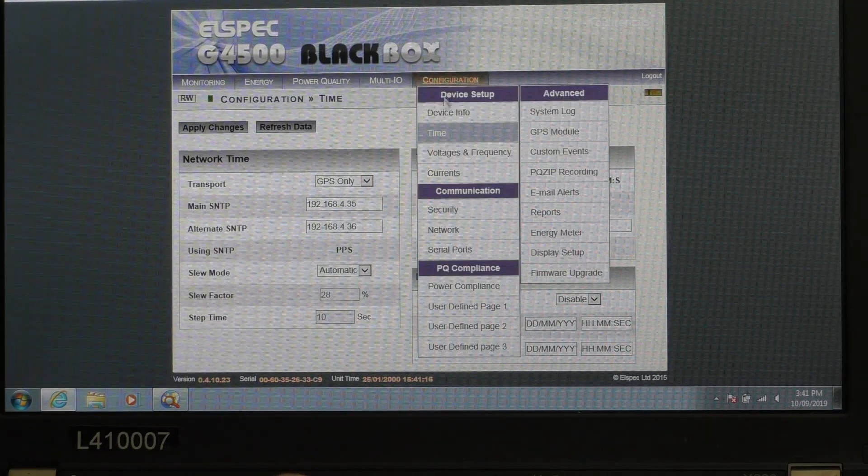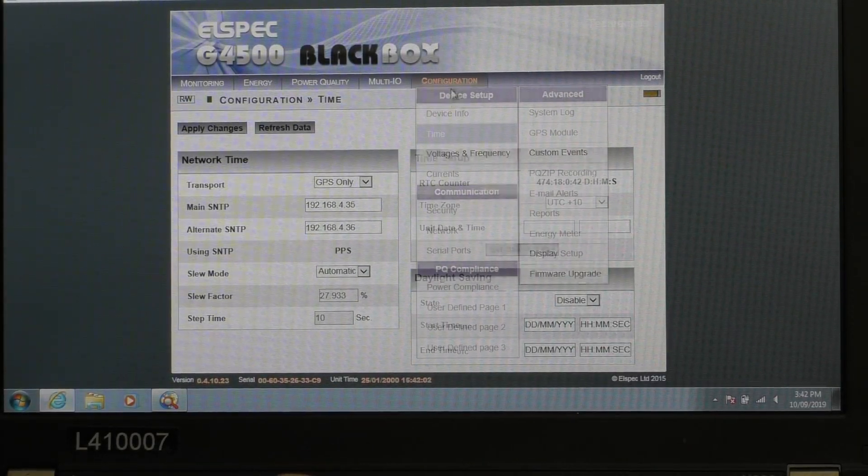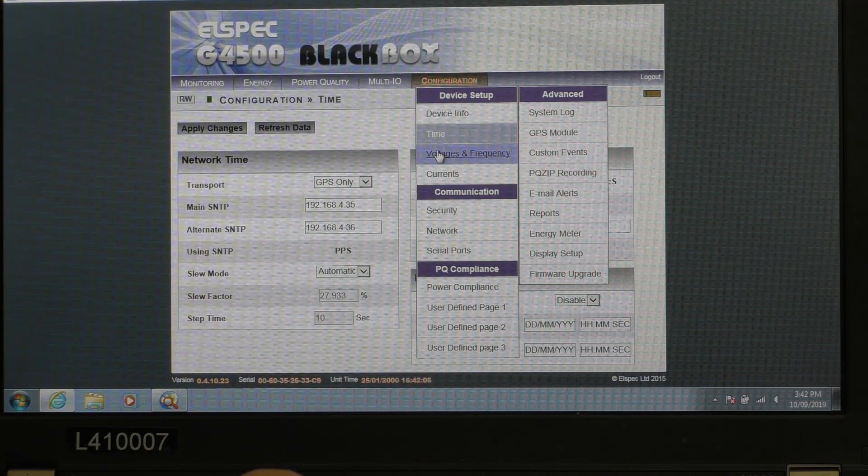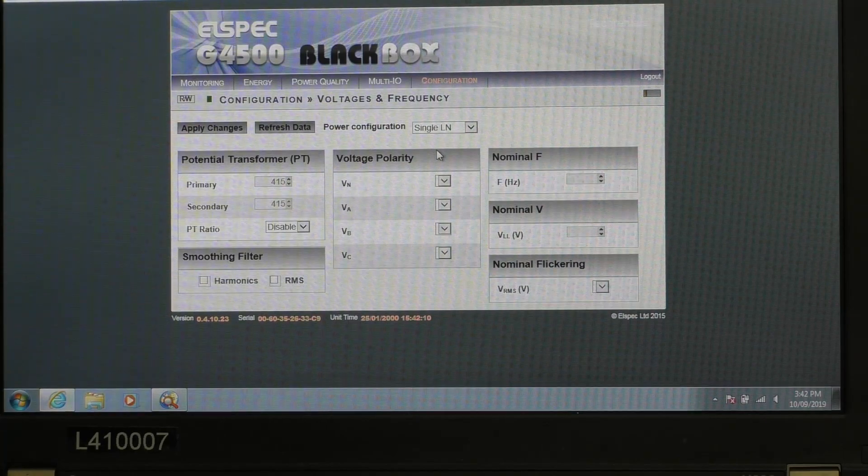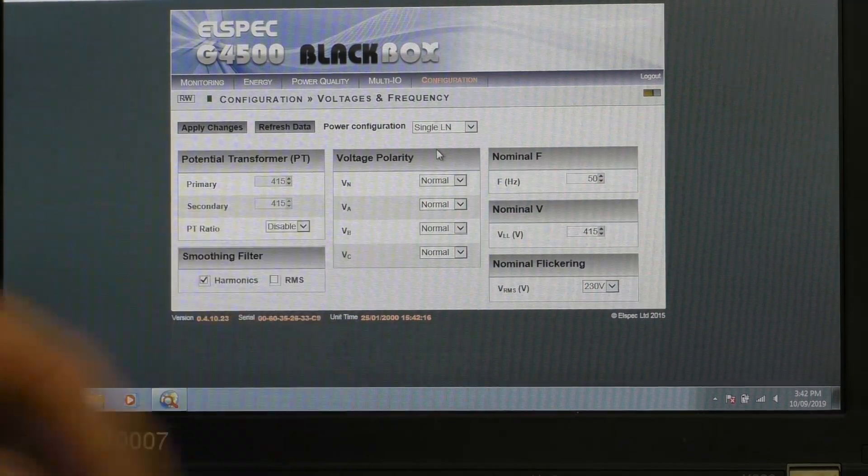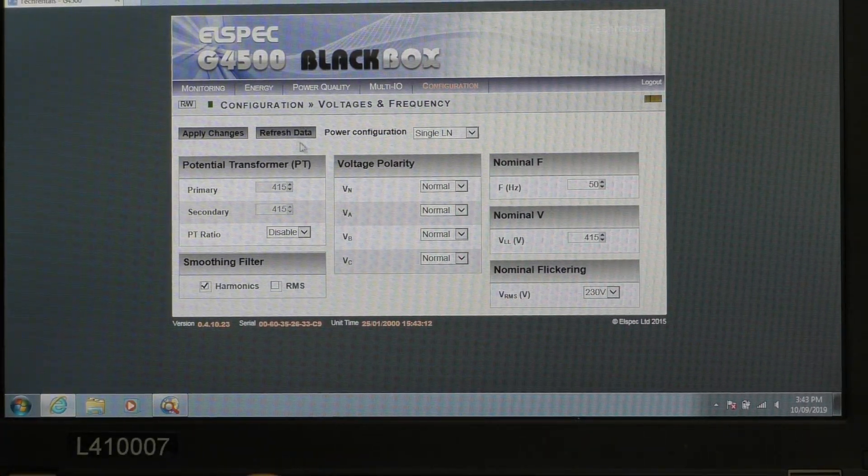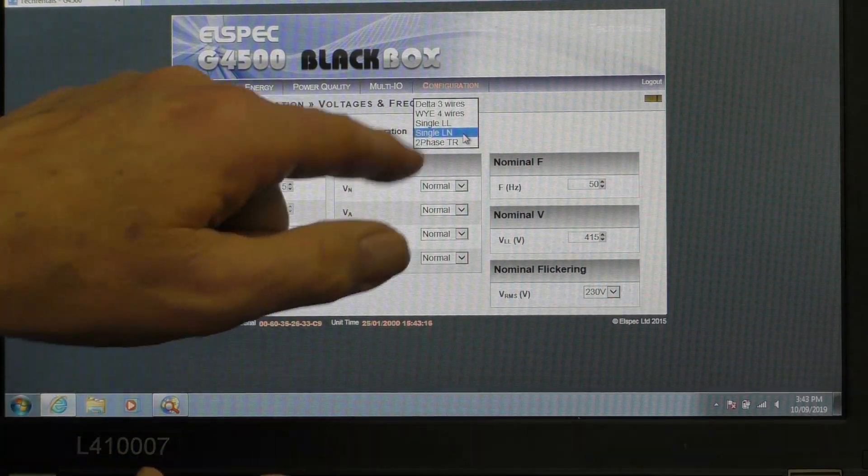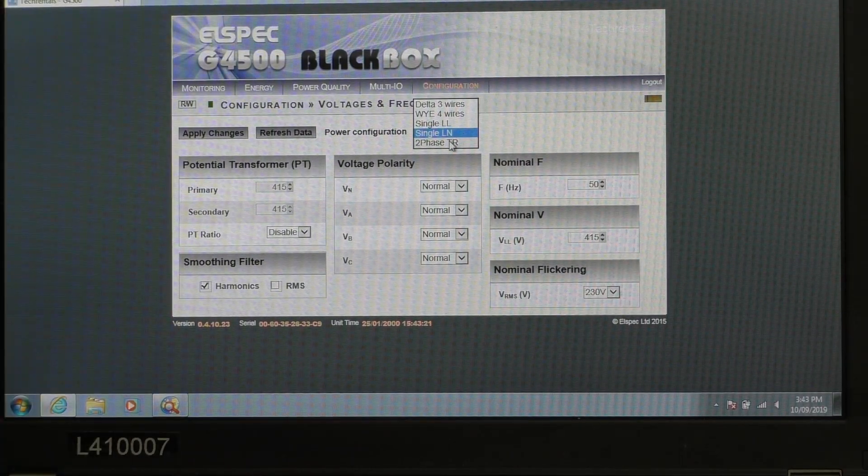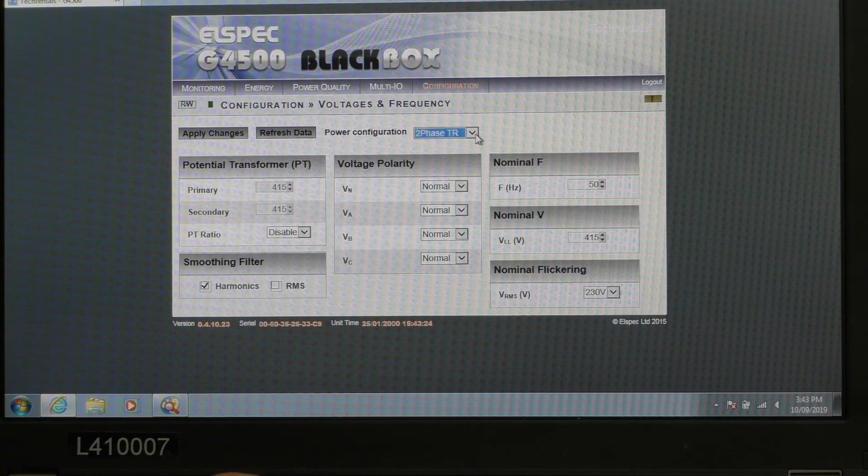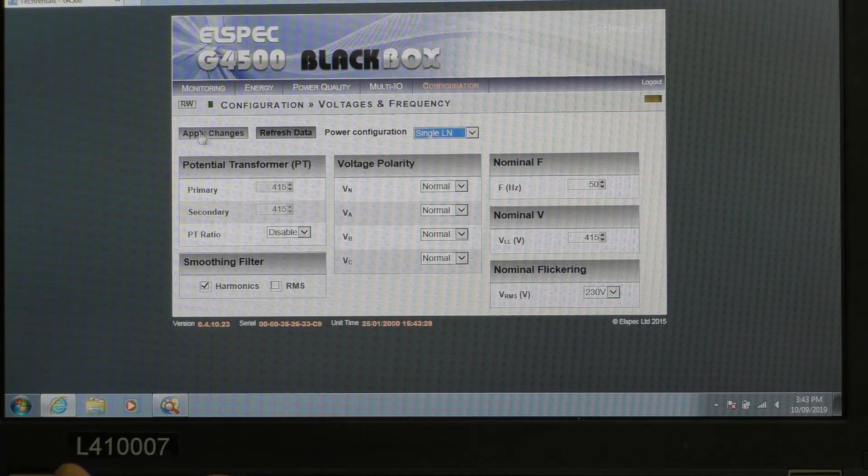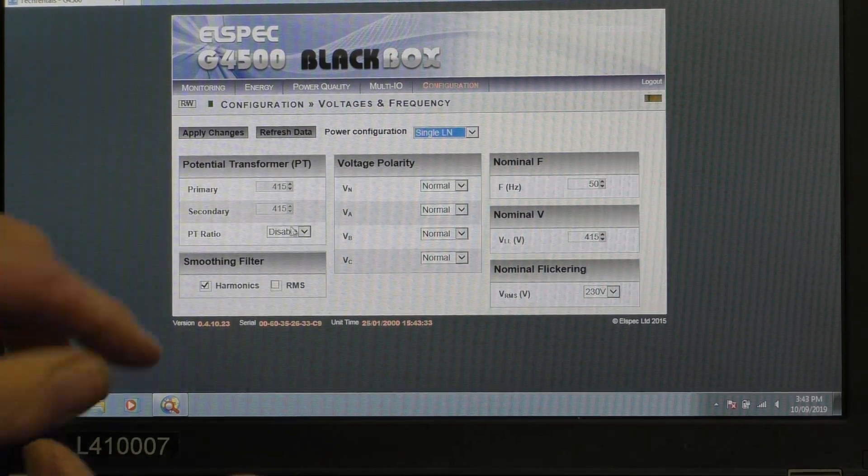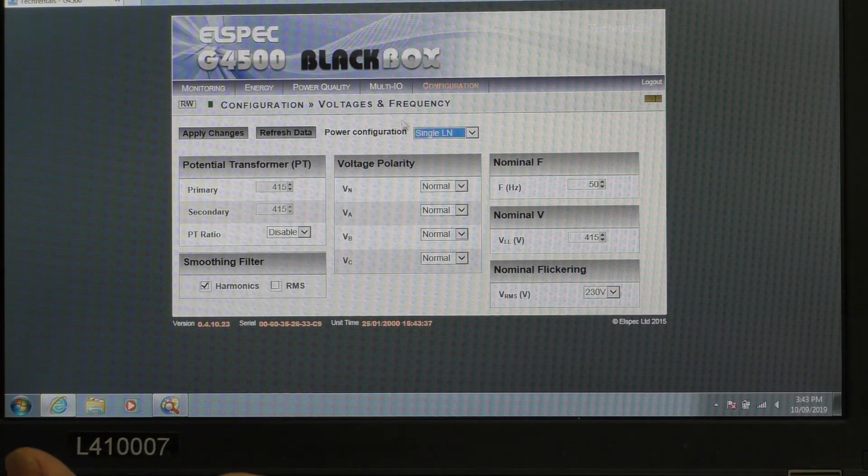Next thing we check is under configuration here, we're just working our way down the list. We're going to go to voltage and frequency and make sure the nominal voltages are correct. Here they are, I've got 230 volts for the RMS, etc. On the voltage frequency thing here, we can set whether we got three wire delta, four Y, four wire single. In this case, we're doing a single with LN. Now, you notice this changes color. We can apply those changes. If we're doing potential transformers, etc. in this case, we're not doing those. So we're okay there.